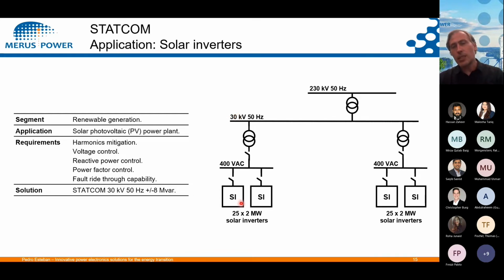The problem of these inverters is that they are creating different kinds of problems, power quality problems, and also many times, depending on the country and the grid code there, the owners or the operators of these solar power plants need to be able to provide certain ancillary services. So, for example, solar inverters typically produce harmonics, so harmonics are always an issue. If you're operating the whole solar power plant, things that are required many times are a certain voltage control capability, reactive power control and power factor control, and even fault ride-through capability. But as I said, these requirements depend many times on the topology, the installation, the country where it's installed, and the grid code that is in use there.